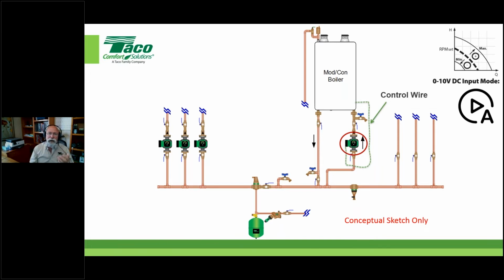The boiler manufacturer is always looking at supply and return temperatures across its heat exchanger. It also, in some cases, has the ability to look downstream, maybe put a sensor out over here and look at the secondary portion of the system, the system side of things. So again, understand that that's all information that the boiler is making decisions on, and it now has the ability to ramp this circulator up and down to maintain something. The majority of the people that have had success doing this, that input is based on a temperature differential across its heat exchanger.